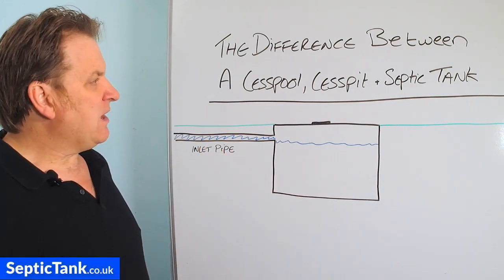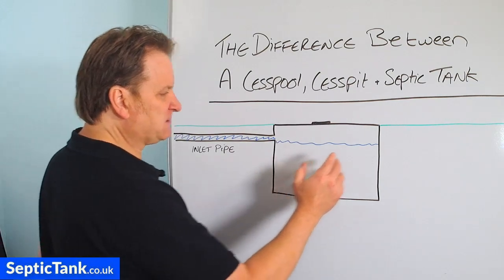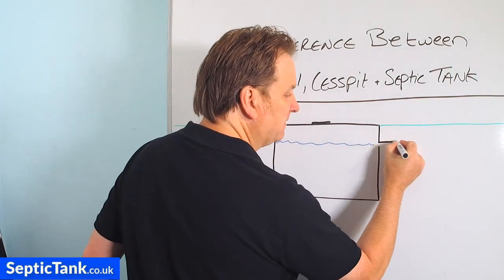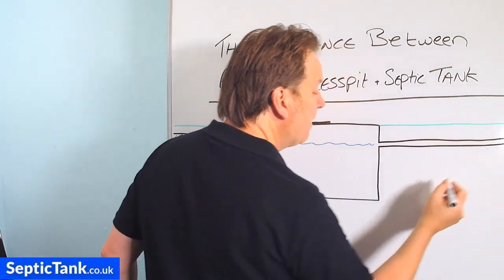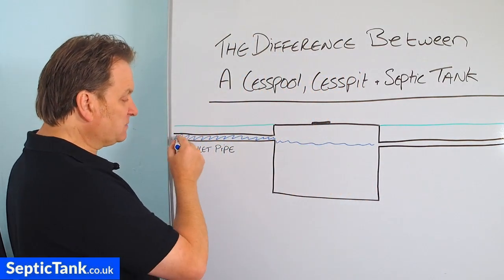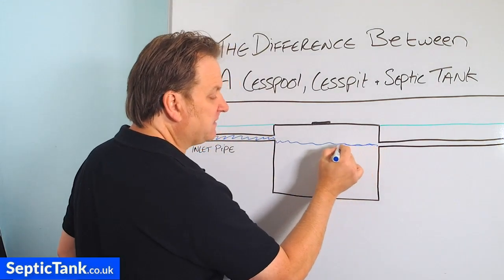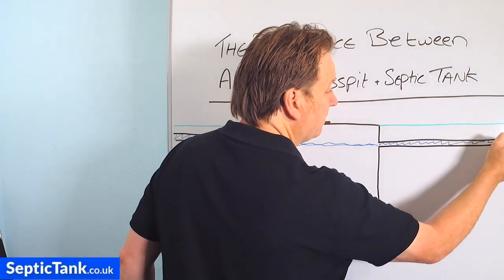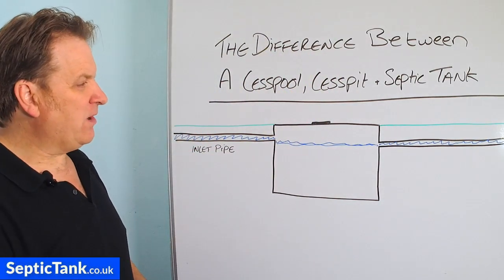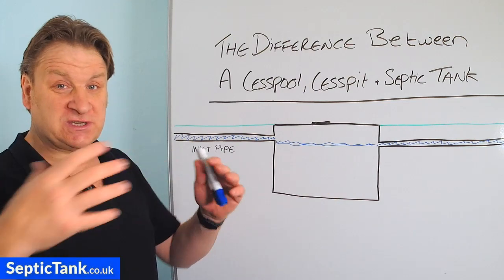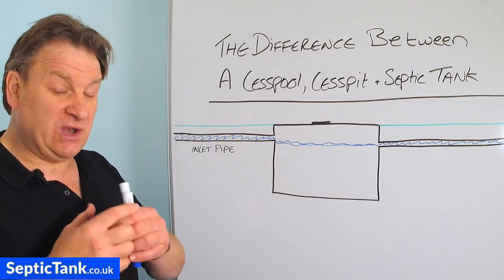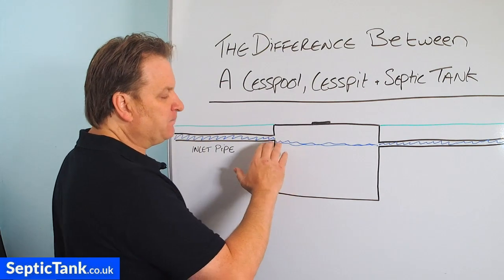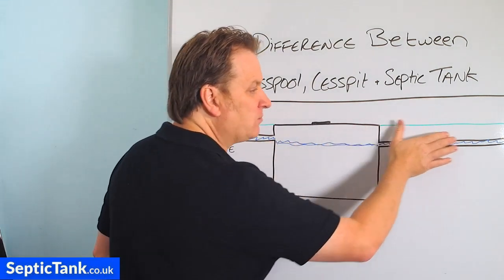Anyway, that's a cesspool. Now a cesspit is exactly like a cesspool, but the only difference is that it's got an outlet pipe. All the wastewater will still come in, fill up to the level of the outlet pipe, and then it will drain away into a soakaway. In the soakaway it will just soak away. The soakaway could be a pit, a herringbone system, or soakaway crates. The point is: liquid comes in, it fills up to the level of the outlet pipe, and then the water will just drain away.